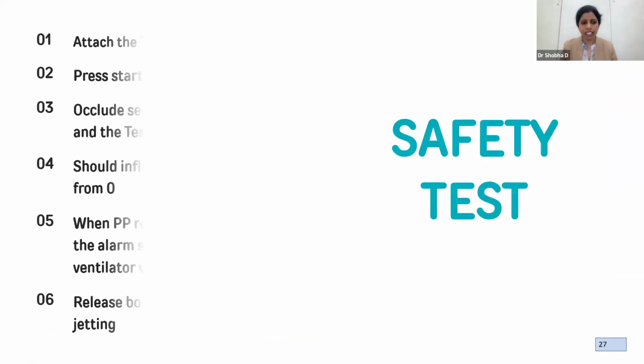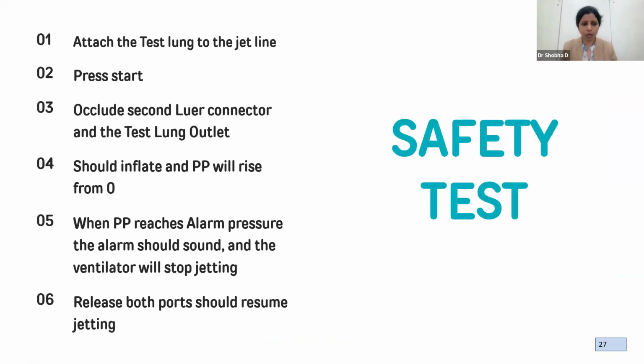So that's one of the safety tests which was done. The other one is, instead of occluding the opening, we can also occlude this second Luer connector and the test lung outlet, which inflates the pause pressure from 0. So when the pause pressure reaches the alarm pressure, the alarm will sound and it will stop jetting. Releasing this, it will resume the jetting.